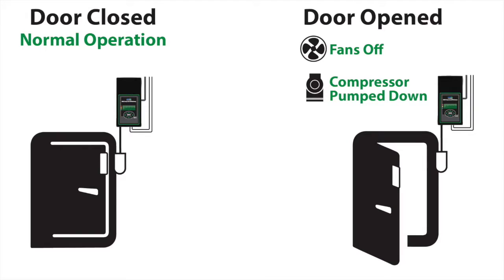With the door switch connected to the controller, the system operates normally while the door is closed. When connected to the controller, if the door is open, the evaporator fans are turned off and then the compressor will pump down.